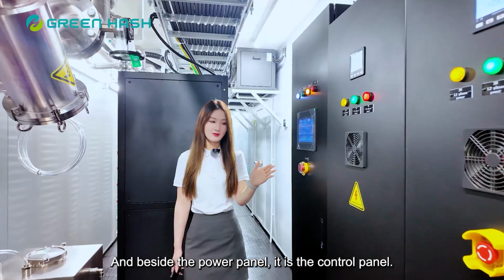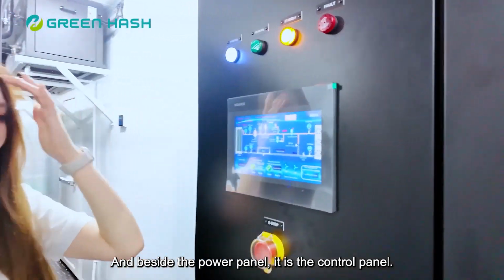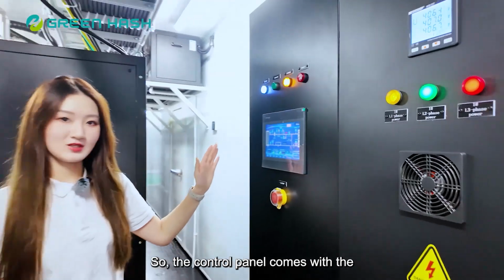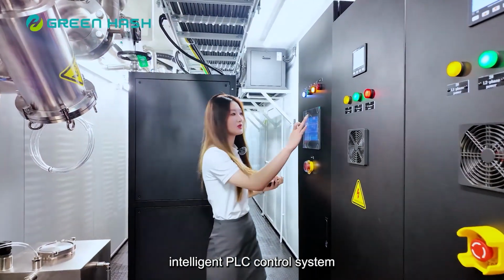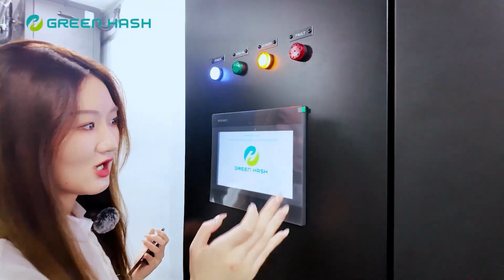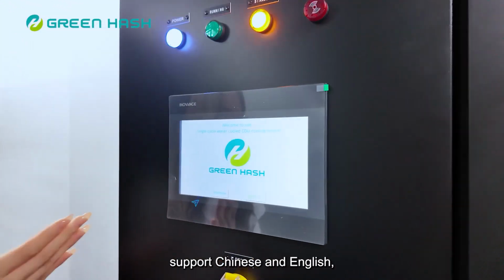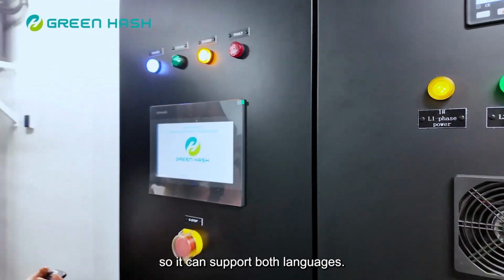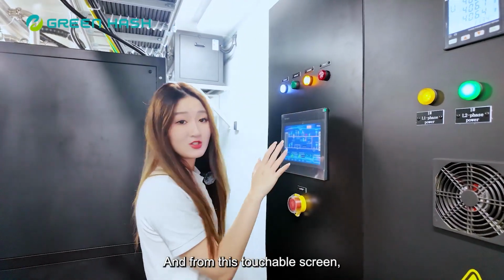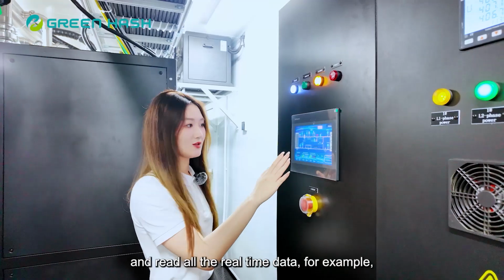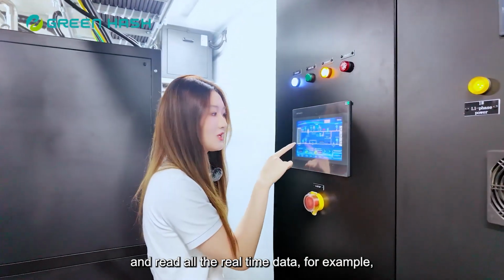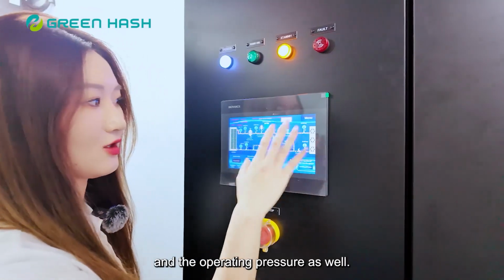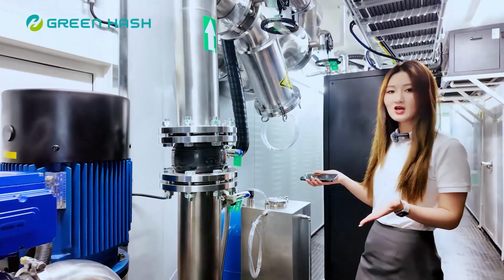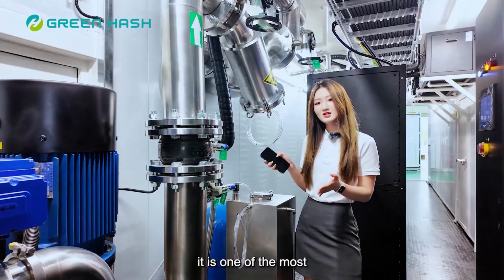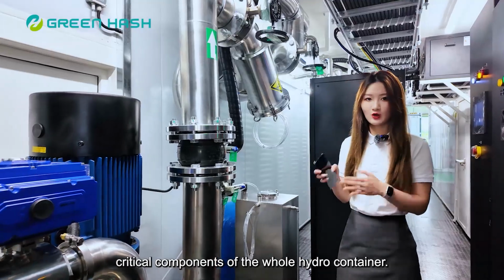Beside the power panel is the control panel. The control panel comes with an intelligent PLC control system. You can see from here, the intelligent PLC control system supports both Chinese and English. And from this touchable screen, it can monitor and read all the real-time data, for example, the inlet temperature, the outlet temperature, and the operating pressure as well. And this section is the coolant distribution unit. It is one of the most critical components of the whole hydro container.